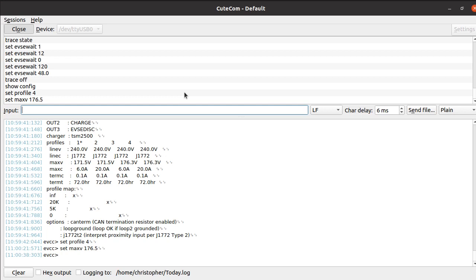The other thing I'd like to change is the termination current. When I'm charging, the charger will keep going until it's less than 0.1 amp, and when it's less than that, it'll stop the charging. That takes a long time at the top of the charge. What it means is when I'm charging out and about, waiting for it to charge up, I don't know when it's full. So if I can have it turn off a lot earlier, it'll charge up pretty much full and then turn off, and that'll be fine. So let's change the termination current to 1 amp.